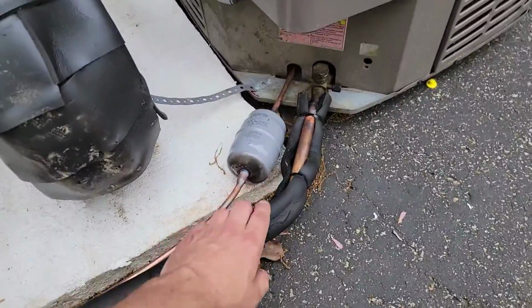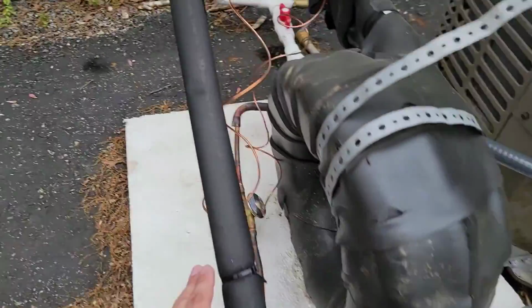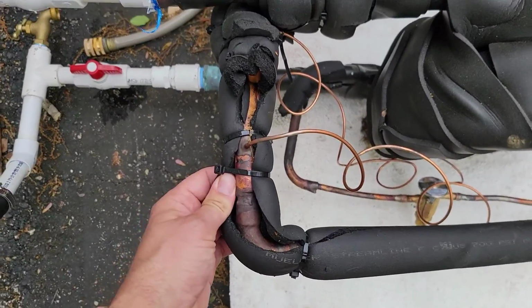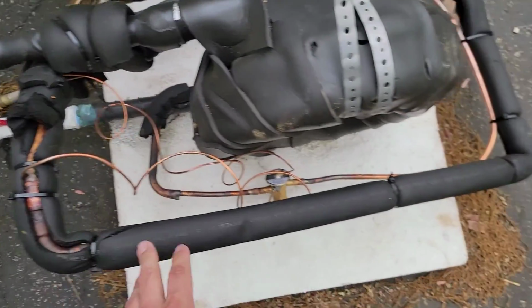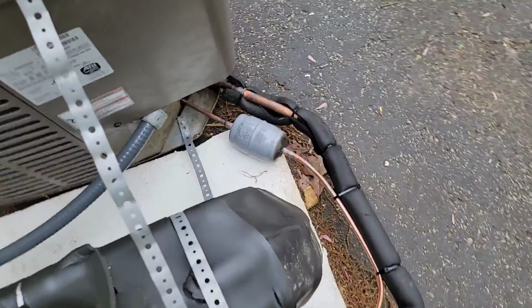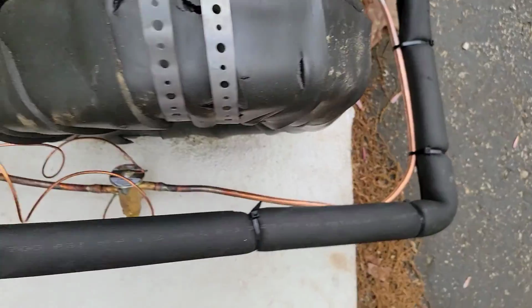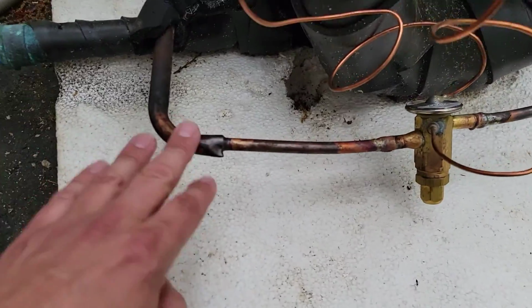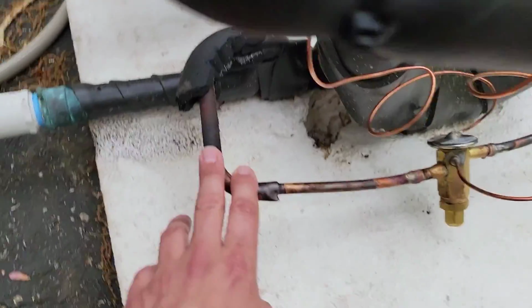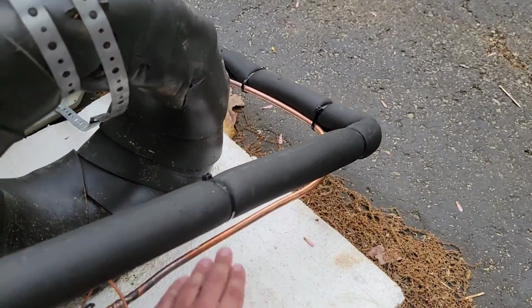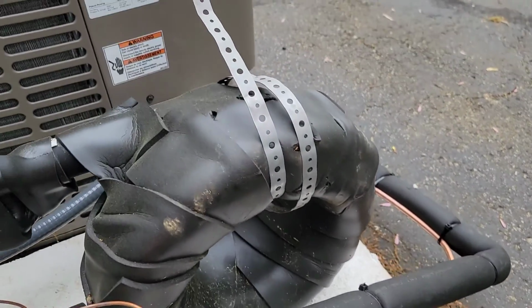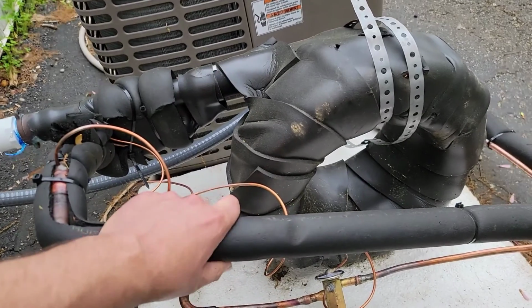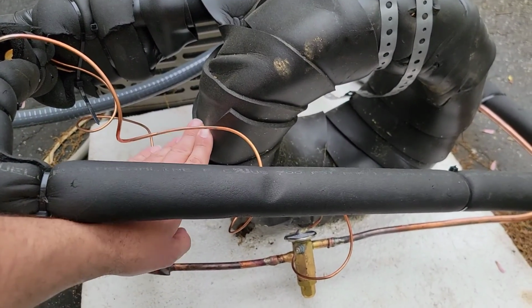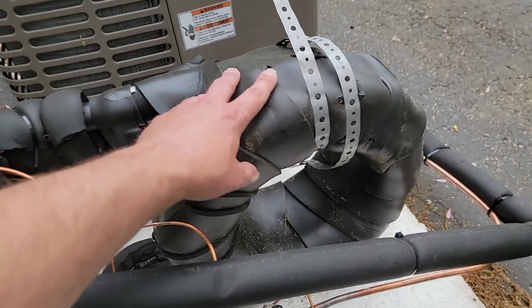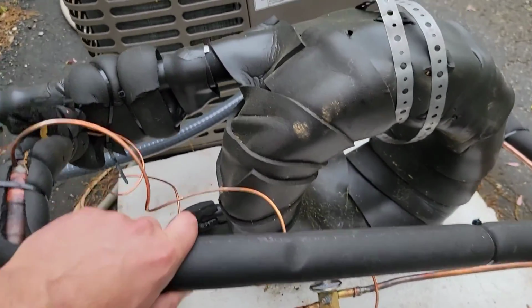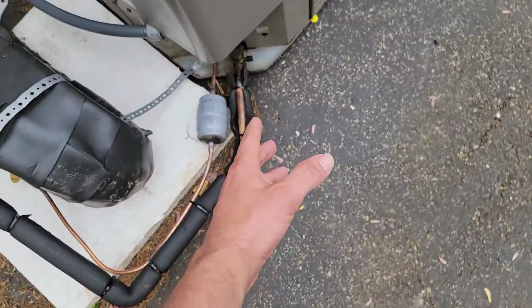So what I did was I tied in the suction line, okay, into the bigger line of the coaxial, which is about the same size as this tubing, which is 3/4 tubing. And then I've got 3/8 tubing here, which is the liquid line. And I've got it going into the TXV and then entering into the coaxial, okay? And the way this flows is, it flows in from the liquid line into the coaxial, and then it boils off.